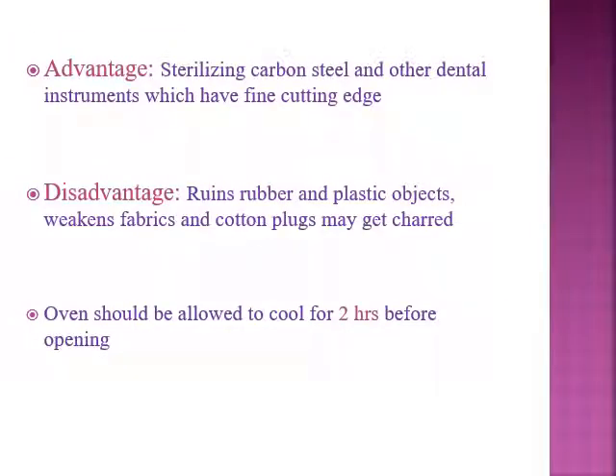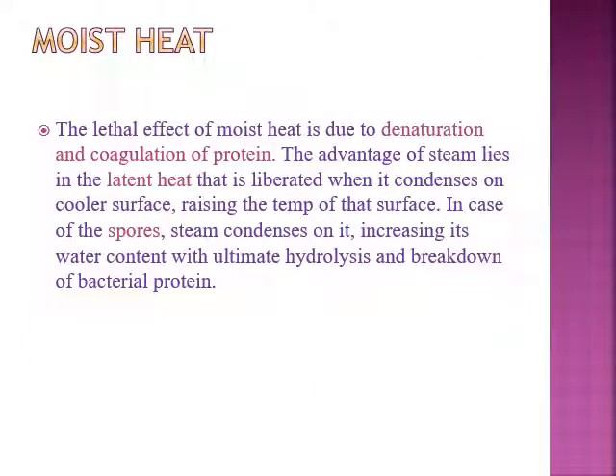So advantages are the sterilization of carbon steel and other dental instruments which have a fine cutting edge. And the disadvantage, it ruins rubber and plastic objects, weakens fabric, and cotton plugs may get charred. So the oven should be allowed to cool for 2 hours before opening. Then come to the moist heat.